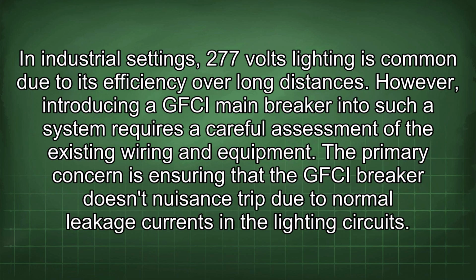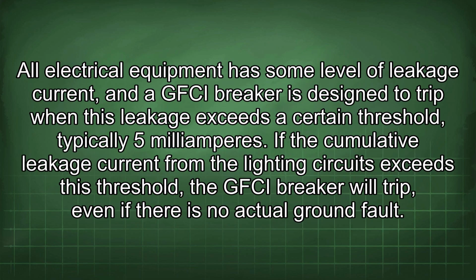In industrial settings, 277 volts lighting is common due to its efficiency over long distances. However, introducing a GFCI main breaker into such a system requires a careful assessment of the existing wiring and equipment. The primary concern is ensuring that the GFCI breaker doesn't nuisance trip due to normal leakage currents in the lighting circuits. All electrical equipment has some level of leakage current, and a GFCI breaker is designed to trip when this leakage exceeds a certain threshold, typically 5 milliamperes. If the cumulative leakage current from the lighting circuits exceeds this threshold, the GFCI breaker will trip, even if there is no actual ground fault.